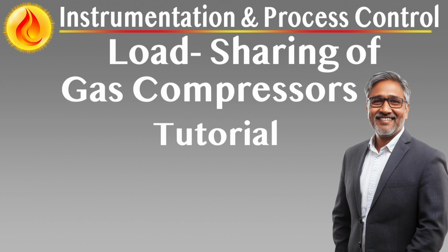Summary. Recycle balancing is a precision enhancement in parallel compressor control architecture that ensures coordinated and efficient surge protection during unavoidable recycling. By aligning anti-surge valve behavior across the compressor network, it protects equipment from uneven stress, enhances system responsiveness, and upholds operational stability. This function underscores the importance of intelligent controller communication in modern compressor trains, delivering not only safety and protection, but also measurable gains in performance, efficiency, and lifecycle reliability.